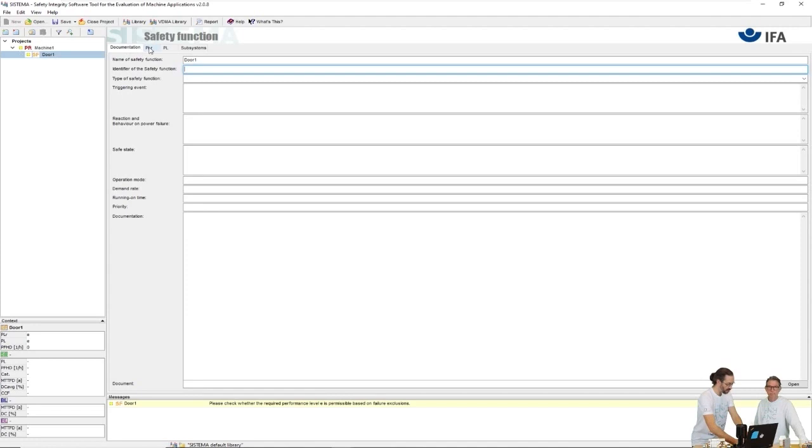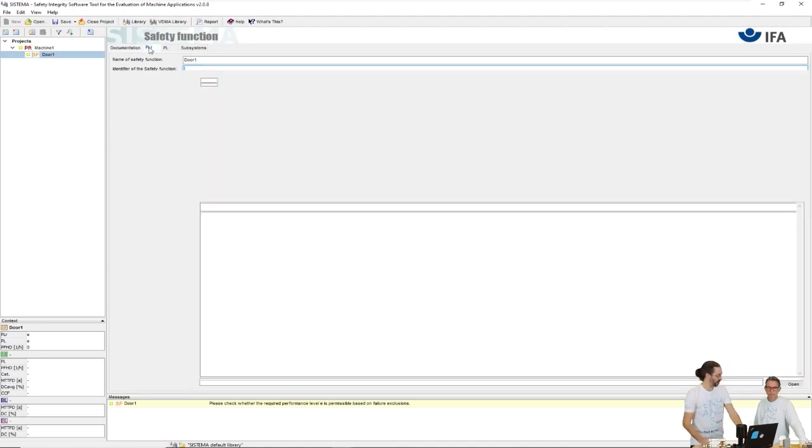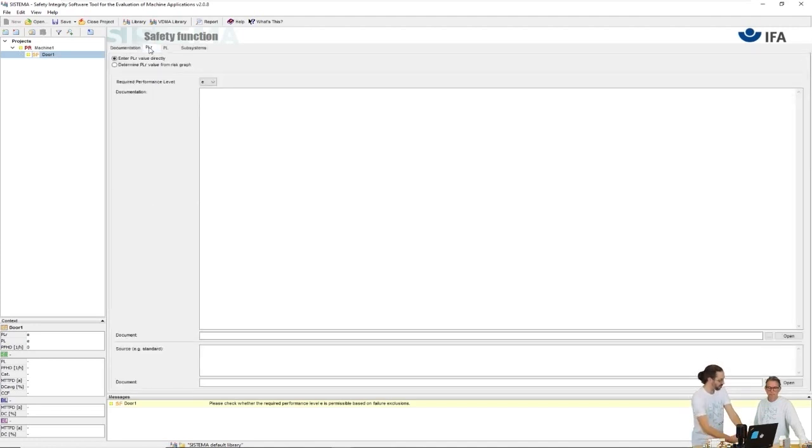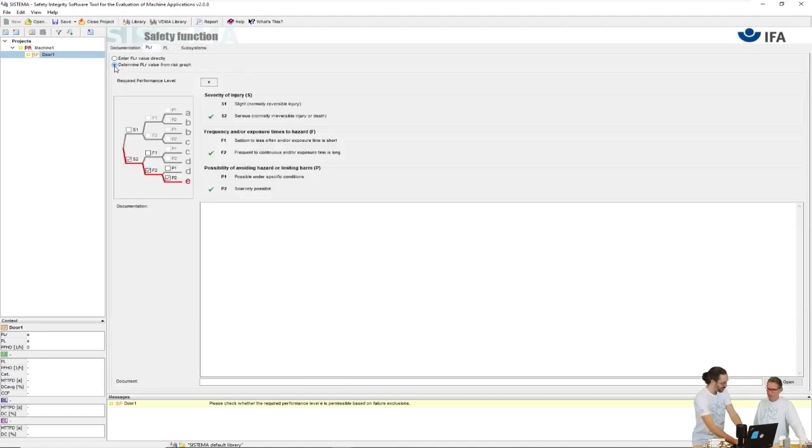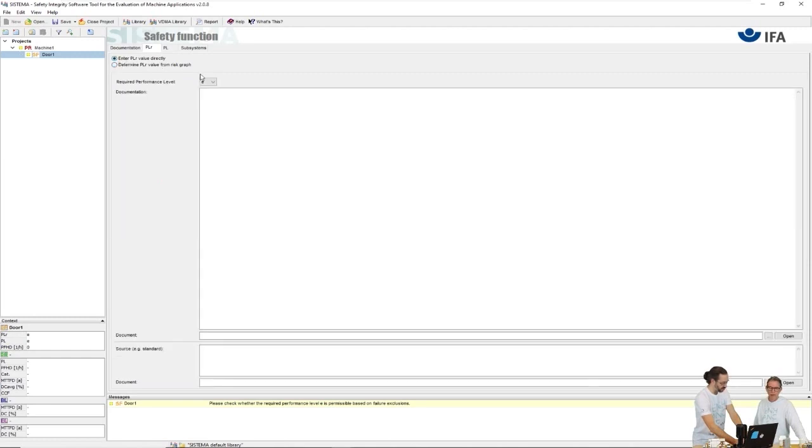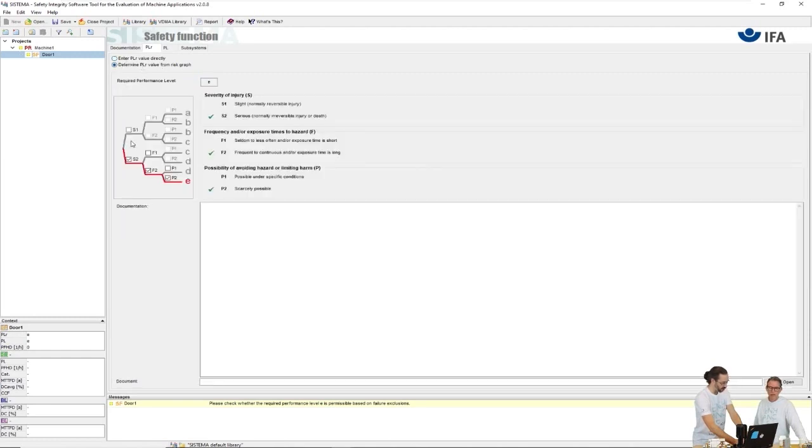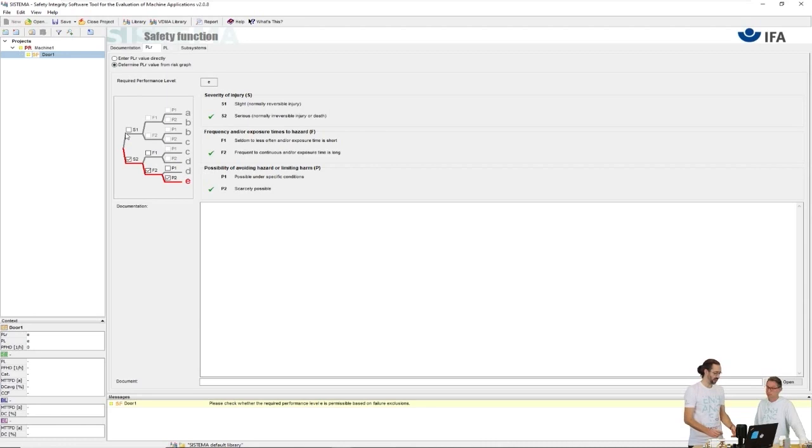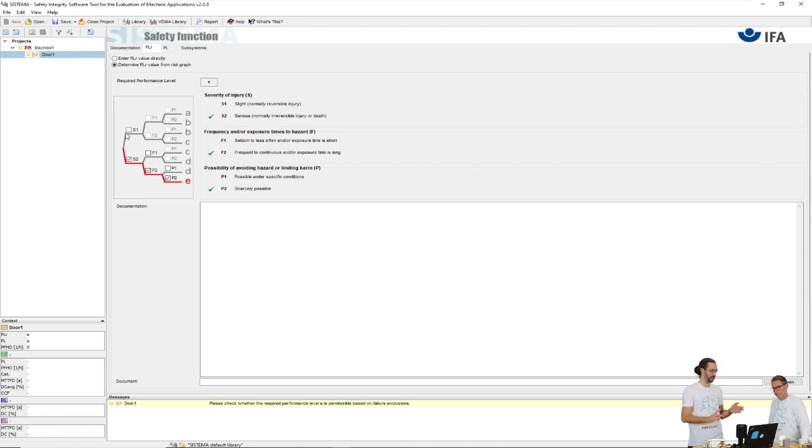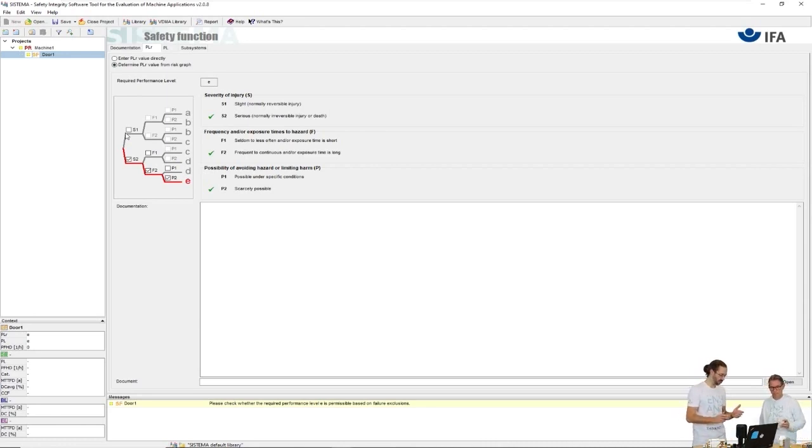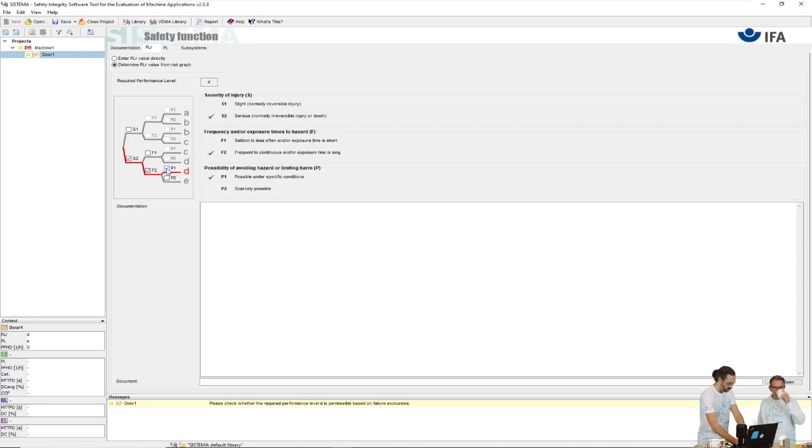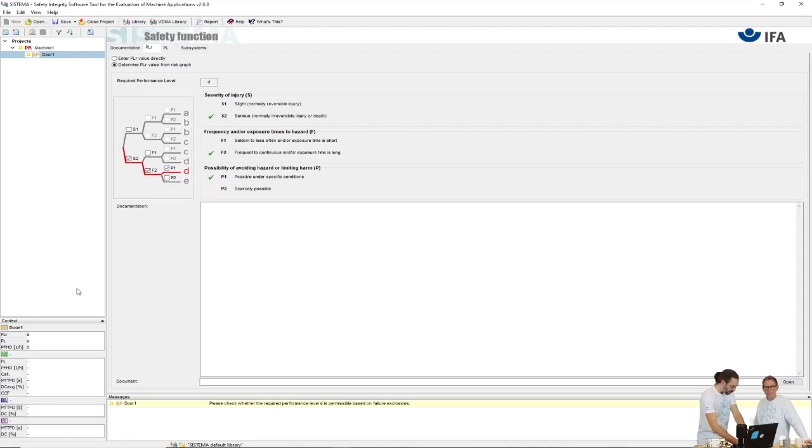First we say the door one had a PL required - you said PLD. Either enter it here directly or if you want you can do this exercise where you look at the severity, frequency and possibility of avoidance. We do like this, then we get PLD. Then we also down here see for safety function door one the target is PLD.